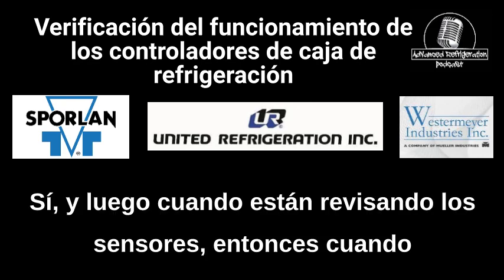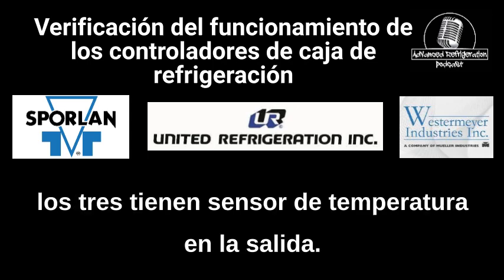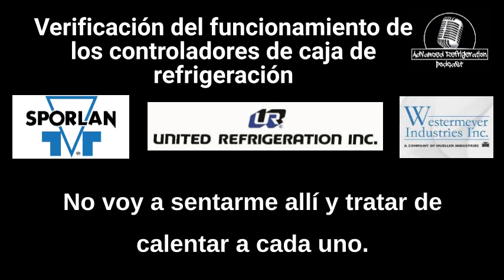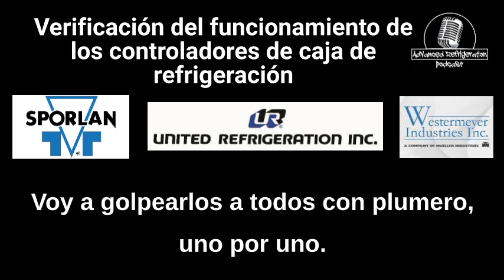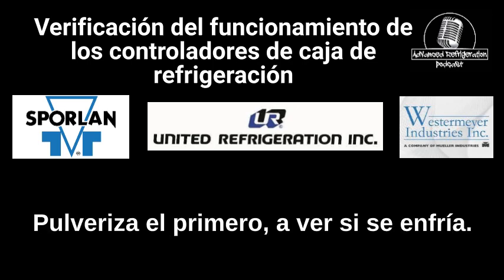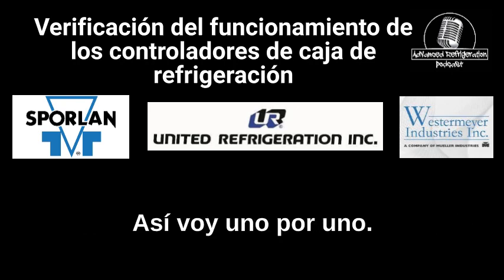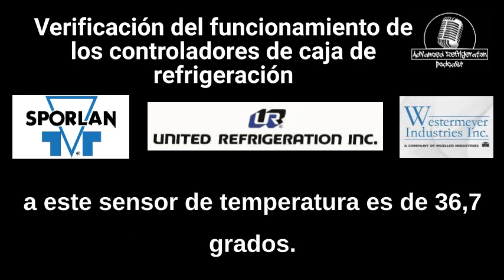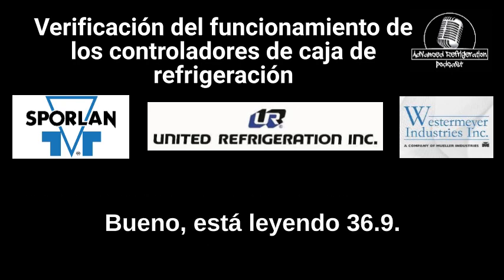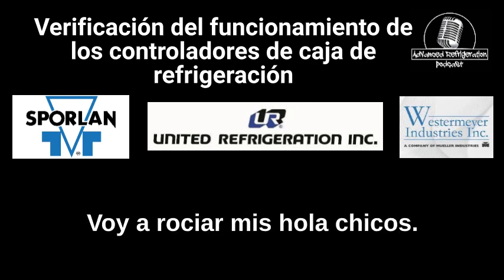And when you're checking sensors, to make sure they're in the right spots, like if it's three coils in one case and all three have a temp sensor in the outlet, I'm not going to sit there and try to warm up each one. I'm going to hit them all with duster one by one, duster upside down, spray the first one, see if it gets cold. If the right one gets cold, move on to the next one, spray the next one. That way I go one by one. I'm not going to sit there and try to figure out this temp sensor is 36.7 degrees, well, it's reading 36.9, or maybe it's this sensor. I'm not going to waste my time doing that. I'm going to spray them.